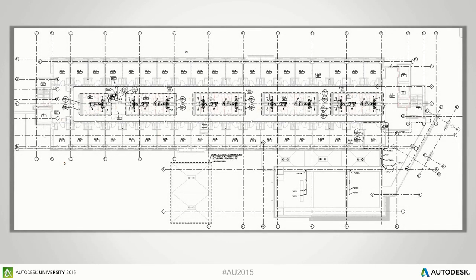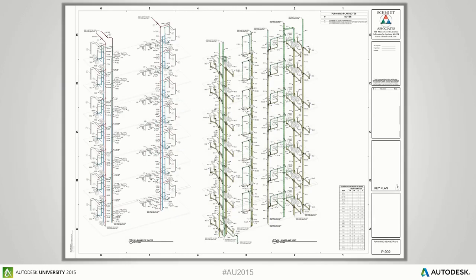Here's an example from an eight-story dormitory where we called out all the interior restrooms and shower areas and then created ISOs. We placed domestic water on the left sheet and sanitary on the right. This one drawing covers eight floors of information — you can see how the overall system changes because the fixtures at the top flow into the system, which picks up from top to bottom, and piping will change at a certain point. All of that is clearly documented in one drawing.